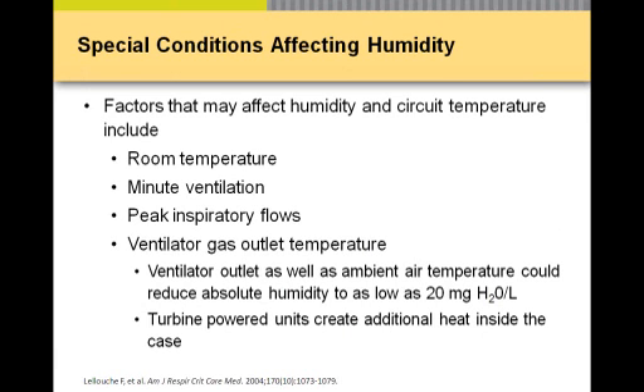Again, you have this gas you think is being humidified, but you look at the circuit and it's dry and the ET tube's dry. Then you need to turn the temp up coming from the device. Because if you put a hot gas into the heater, the gas is already hot, I don't have to warm it up. So it will back off and won't put as much humidity in it as is needed.